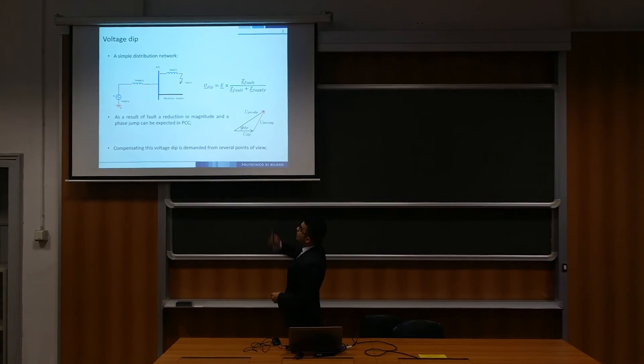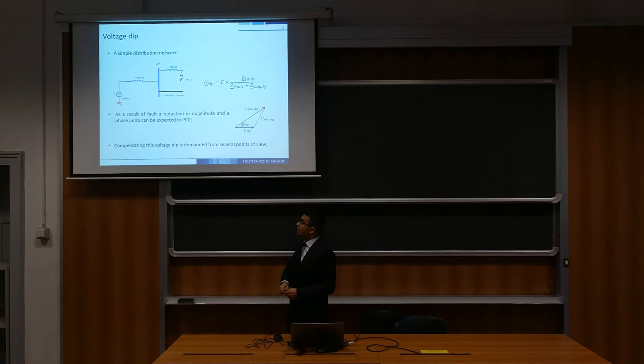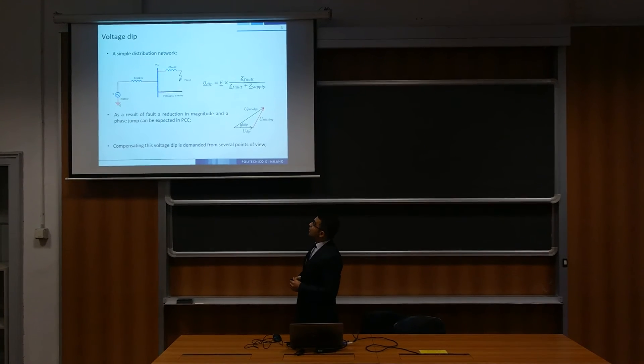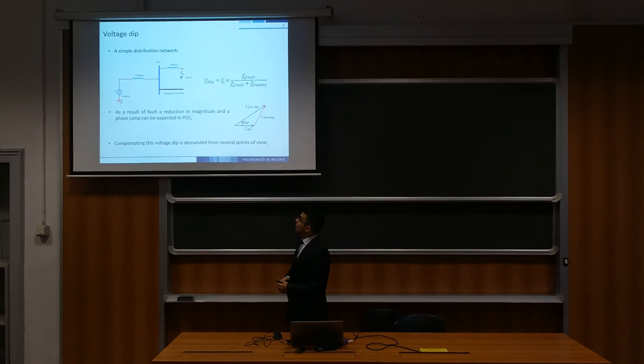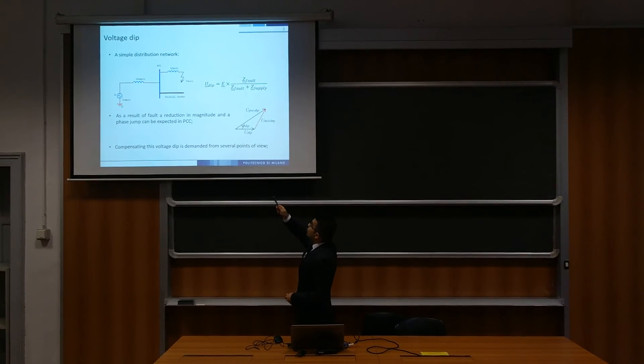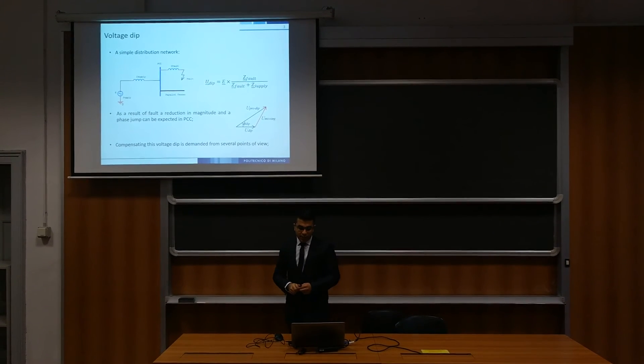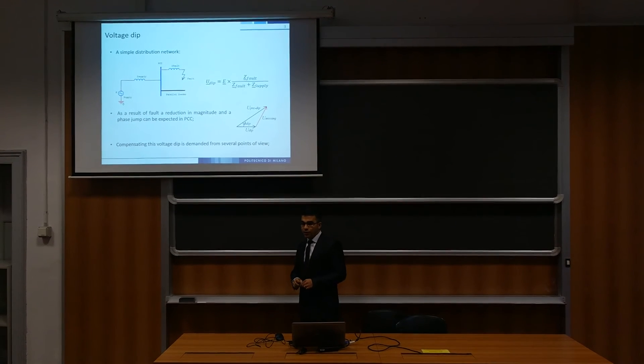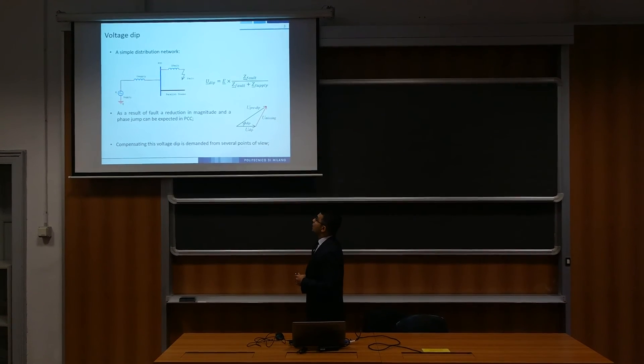As you can see, in a simple distribution network, if a fault occurs on one of the feeders, the voltage at the point of common coupling can be calculated using the voltage divider rule. As a result of the fault, a reduction in magnitude and a phase jump can be expected, as shown in the phasor representation.